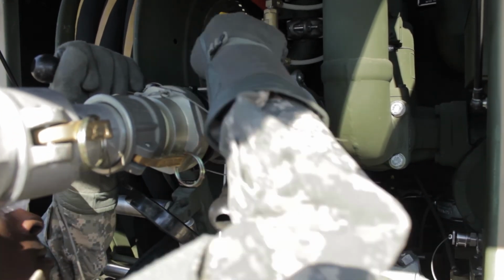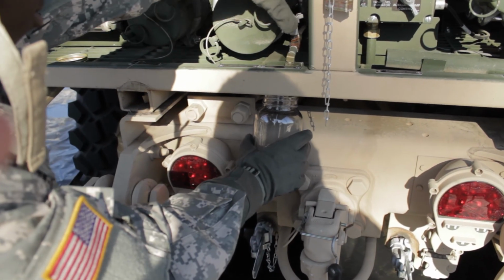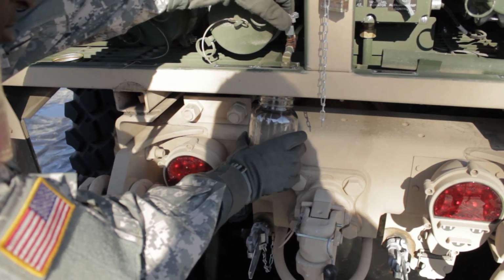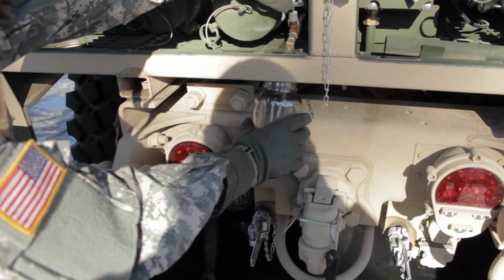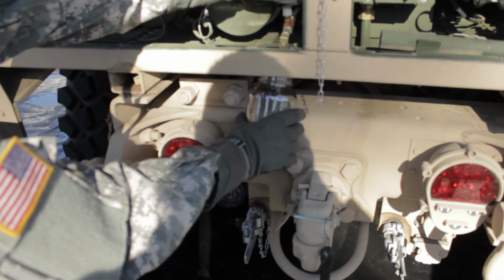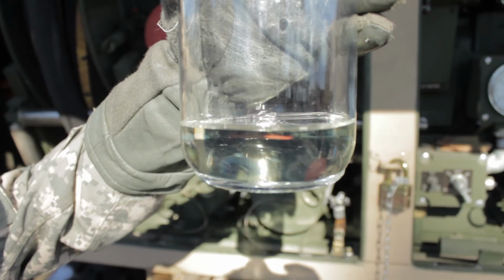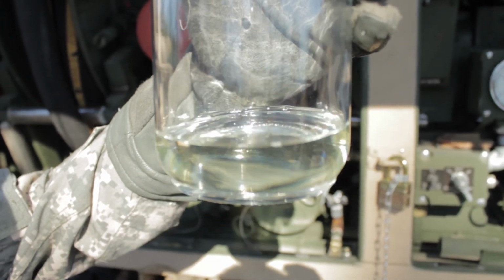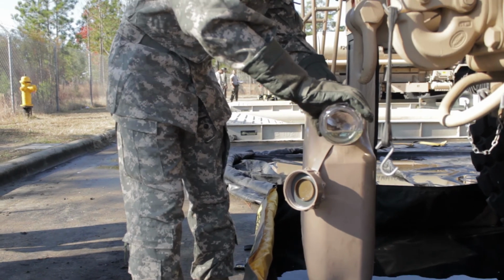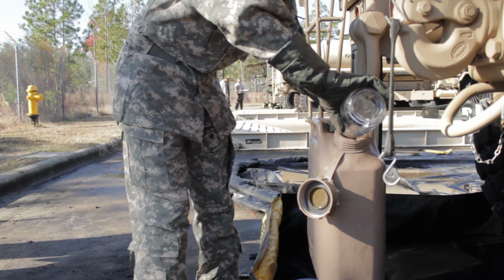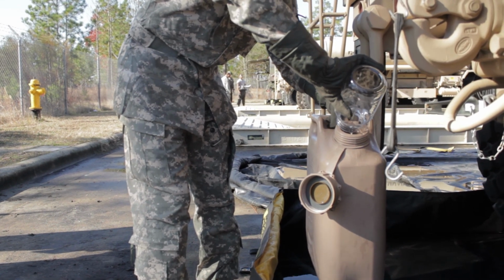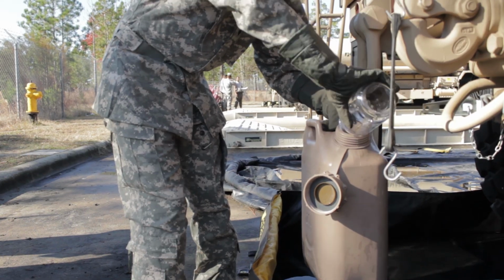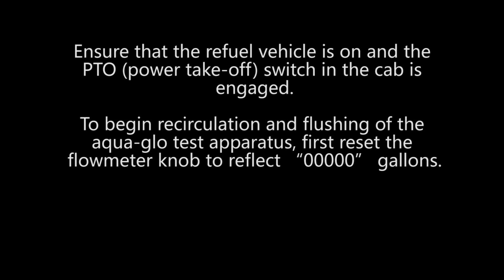To drain water from the filter separator, hold a clean glass container under the small hose coming from the bottom of the filter separator. Open up the V15 drain valve and allow the filter separator to drain of BS&W, bottom, sediment, and water until only clean, clear fuel comes out. Close the V15 drain valve and empty the waste fuel into a suitable container. Note, do not put this waste fuel into the fuel tank of any equipment. Ensure that the refueling vehicle is on and the PTO, power takeoff switch in the cab is engaged.